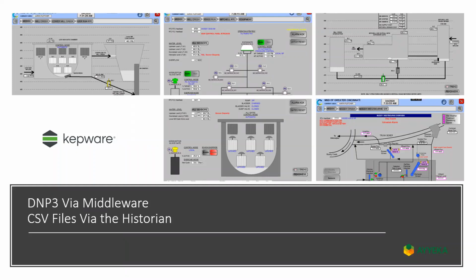In any event, the data you're getting is somewhat historical. In a properly configured system, the delay between an event being identified and read in the field to when it's actually fed into the historian might be on a scale of 3 to 5 minutes, even sometimes 2 minutes, depending on how well things are tuned. But it's always going to be delayed nonetheless, and for that reason, in most enterprises we found, the SCADA system really represents the source of all the information being tracked, and the historian is what's used for analytics. So in a way to feed the analytics system, the best place to feed that data is into the historian itself.